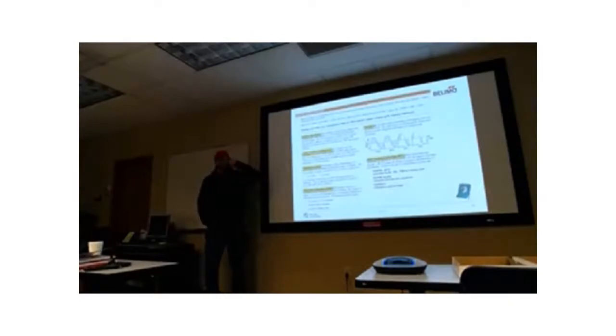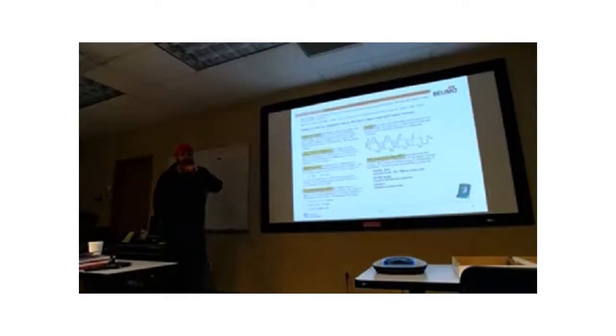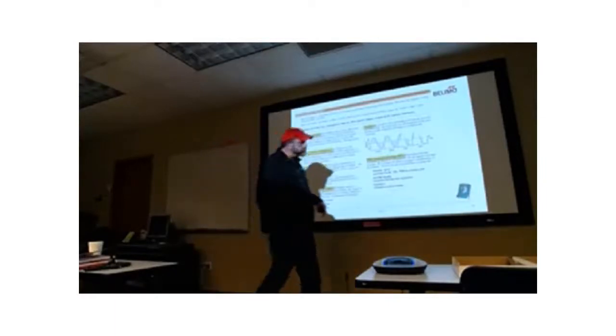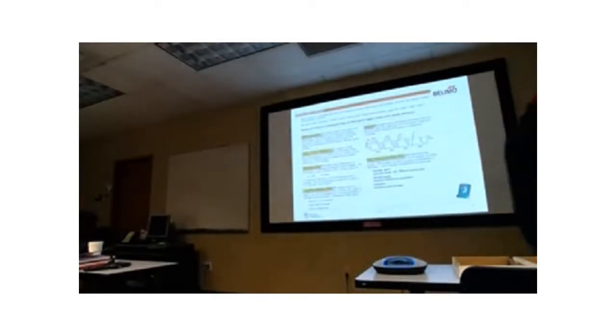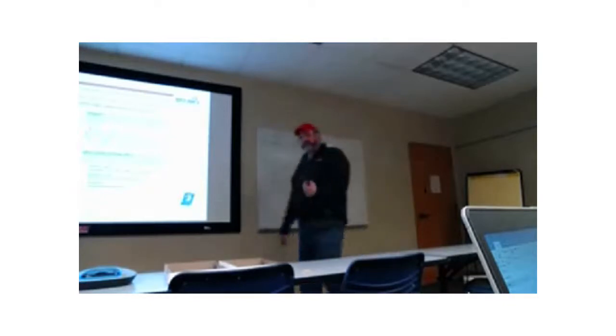Now, with proportional control, one of the advantages is, if we go back over here, I can command the actuator. This is an analog output. I can command that actuator to a specific position, and the feedback can report it exactly, right? Just like in the data centers. Proportional control and feedback sort of go together, because you can command the actuator to a certain position, and you can confirm it's in that exact position.